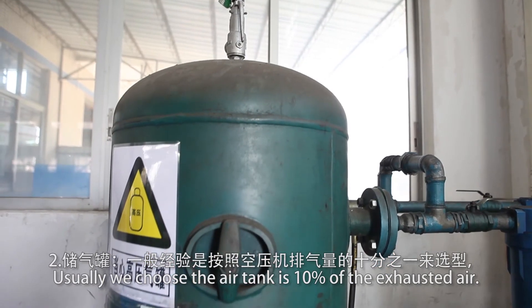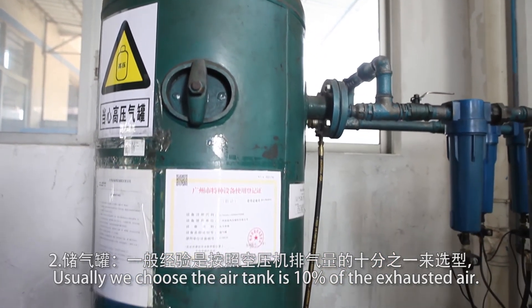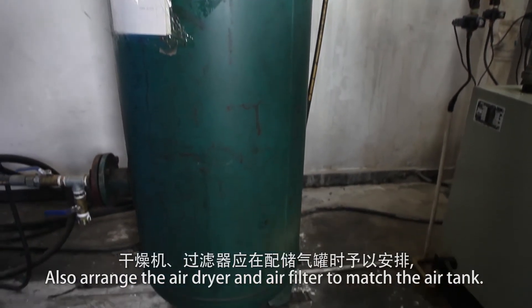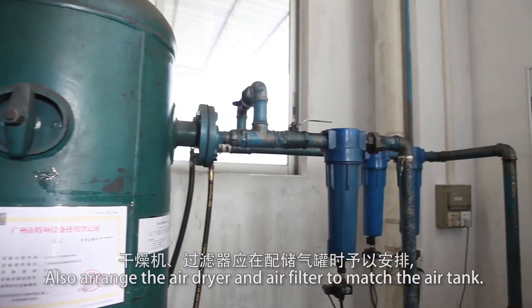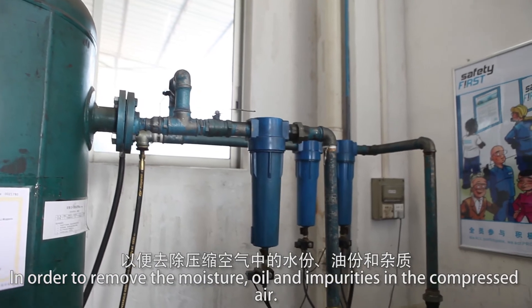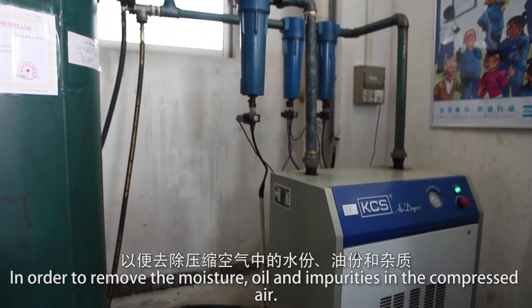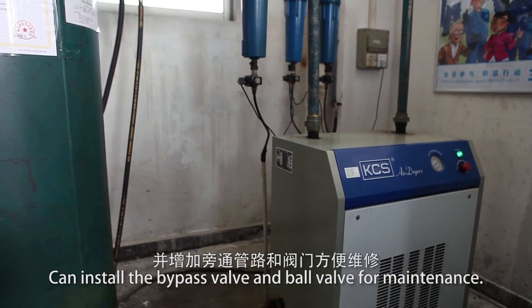For the air tank, typically choose a tank that is 10% of the exhaust air volume. Also arrange an air dryer and air filter to match the air tank, in order to remove moisture, oil, and impurities from the compressed air. Install a bypass valve and ball valve for maintenance.